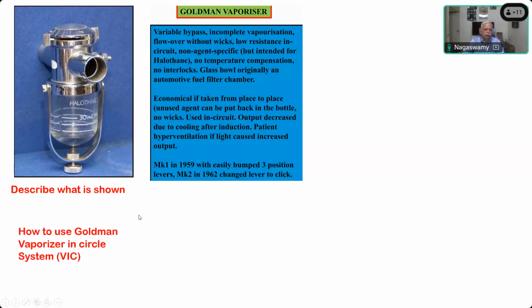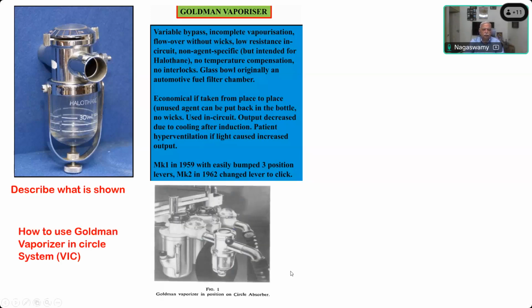How to use the Goldman vaporizer inside the circle system? Many of you would not know. I just thought this picture will help you to see. So this is the Goldman vaporizer attached to the inspiratory limb of the circle system. Okay. So this is the inspiratory limb. This is the expiratory limb. This is the canister with the soda lime. So this is attached to the inspiratory limb, and you can fill it with halothane and open the lever. And what are the advantages of using the vaporizer inside the circuit system?